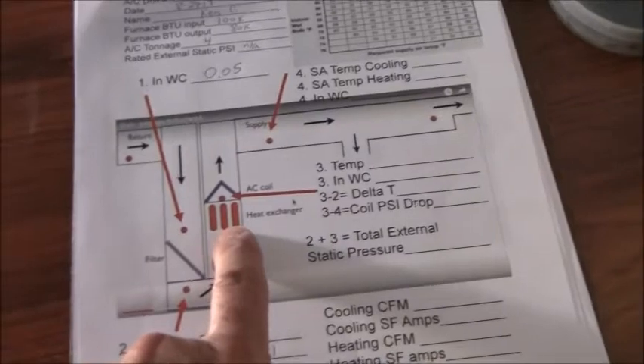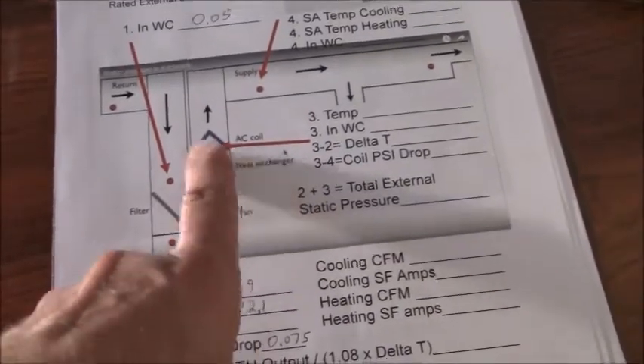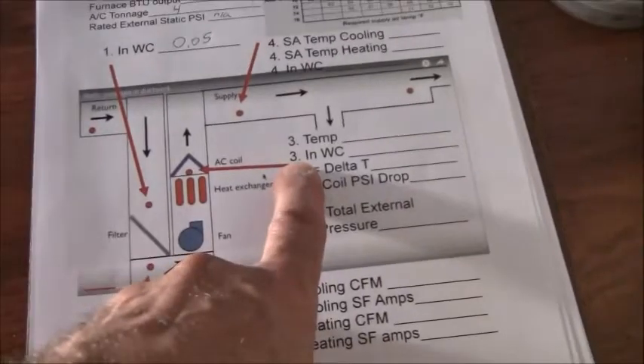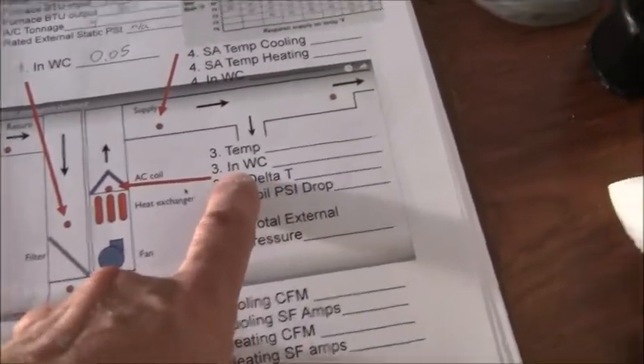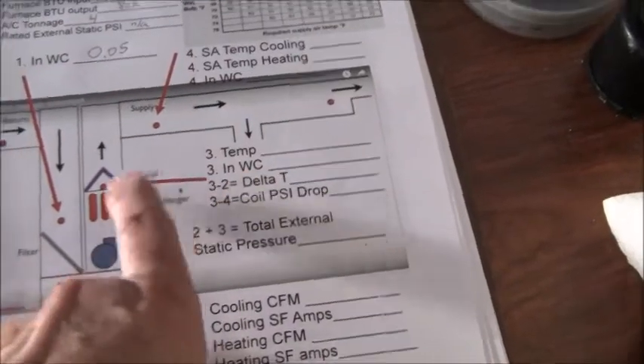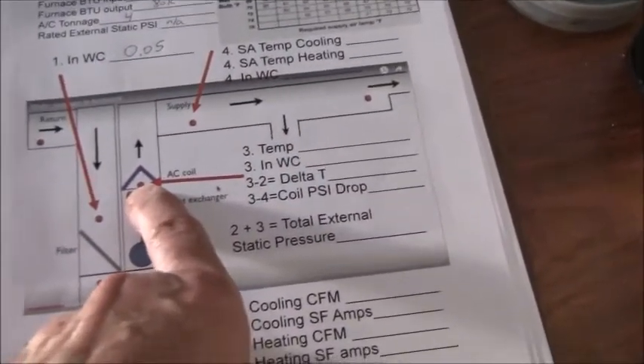Now, we want to get after the coil, the heat exchanger, and before the coil, okay? That's going to be point number 3. I want to know what that is in inches of water column. Now that is going to be a high pressure, not a low pressure. So what I'm going to do is take the 2 probes out of here. I'm going to take the high pressure probe, which is the top one here, and put it between these 2 points. Now, on my unit here, what I did was I drilled a hole right there.